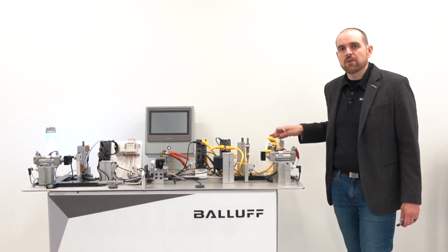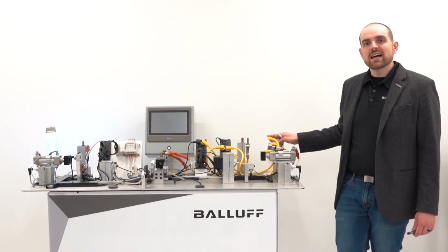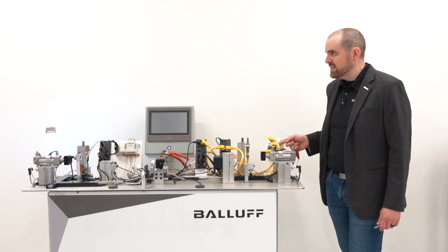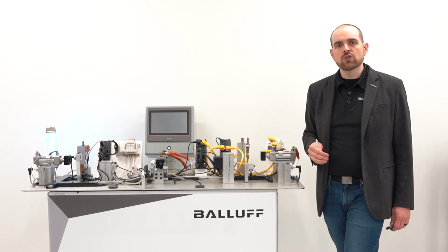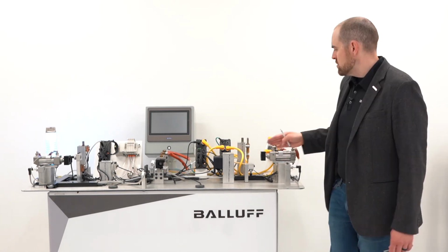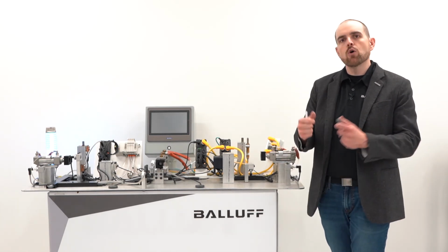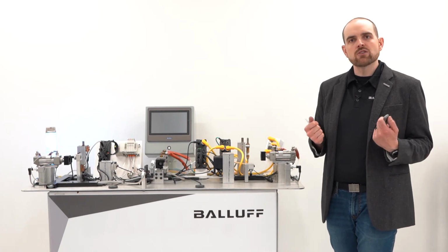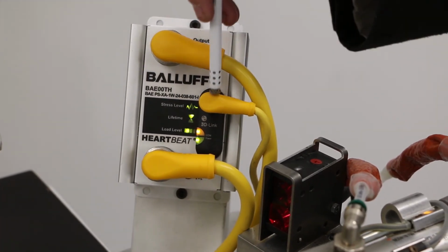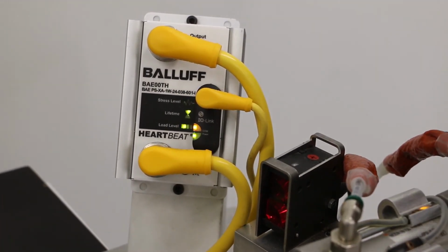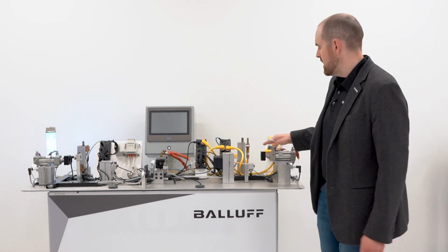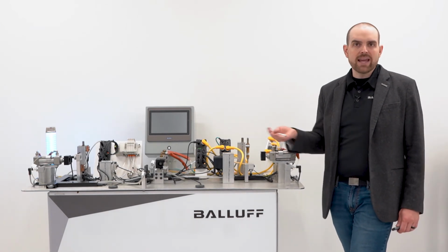Then over here you see a power supply. This is an IP67 power supply. What's nice about this is you can mount it right on the machine outside of the cabinet, and this allows a maintenance person to look and see, do we have good power supply? You know, power supply can be one of those things that's tough to troubleshoot. So if we have it out on the machine, they don't have to open the cabinet and risk any issues like arc flash or anything by opening a cabinet. So we can have the power supply right on the machine, and with an IO-Link connection on the power supply, we can get information like how much current am I drawing or how much service life is remaining. We can get warnings like how much life remains in the power supply.